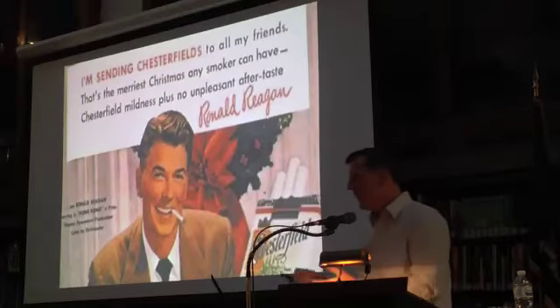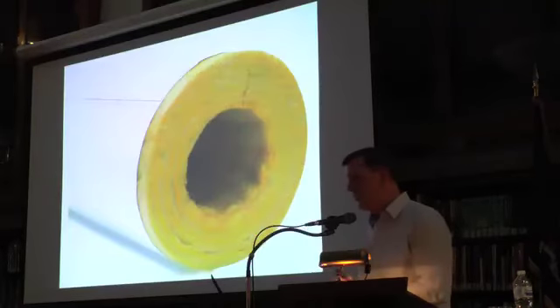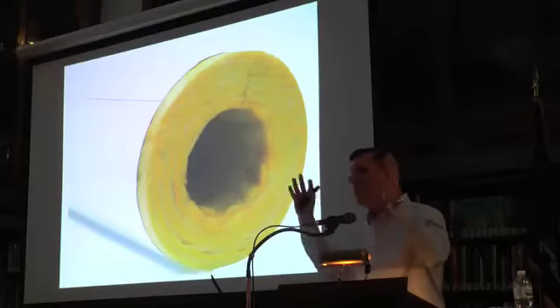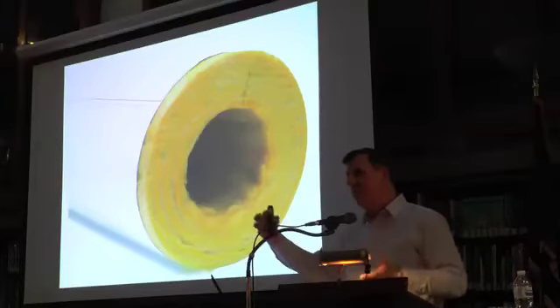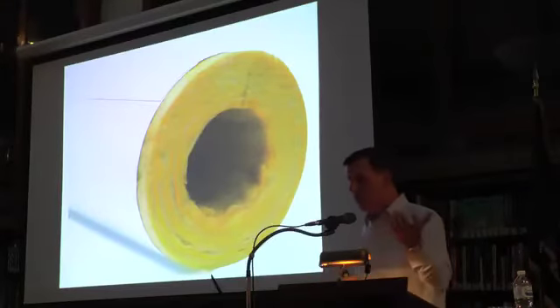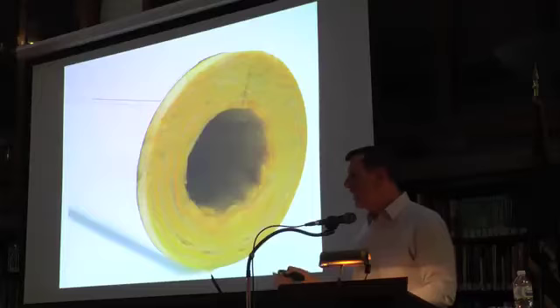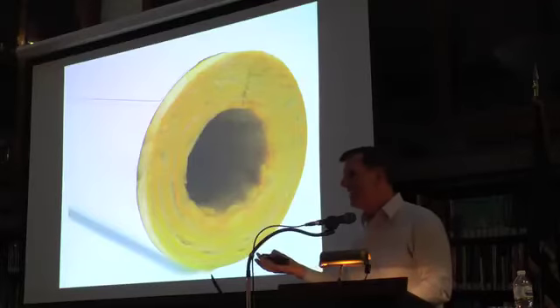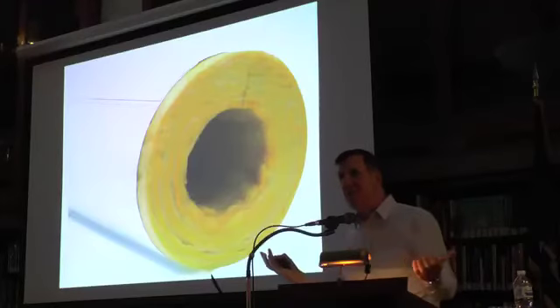And when we take the asbestos off, a lot of times it does not get replaced with fiberglass insulation because we don't want to spend the money. So we had a building that was heating okay, but now we remove all the pipe insulation, and suddenly the stuff that's nearer the boiler is getting hot, and the basement's nice and warm, the garage is warm, because we got all the asbestos off, but upstairs is cold. So some knucklehead comes along and raises the pressure, thinking that somehow if you raise the pressure, you're going to increase the output of the boiler.